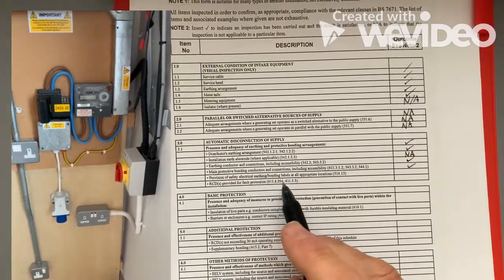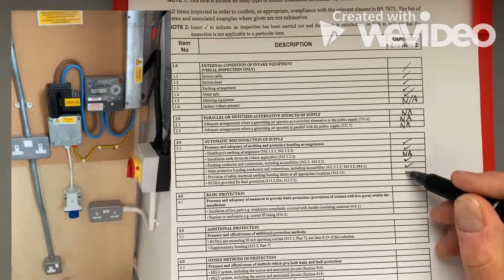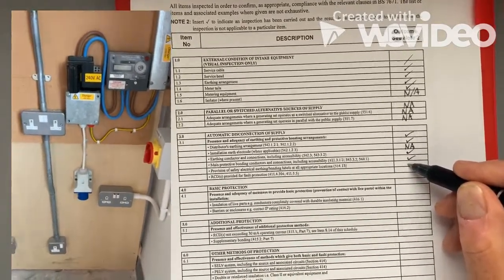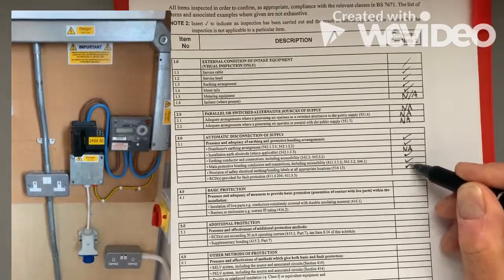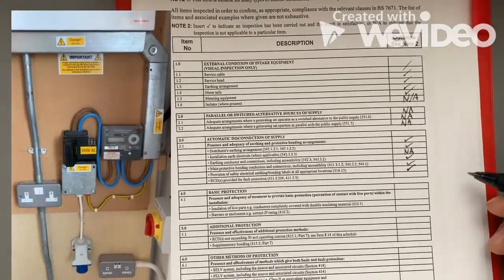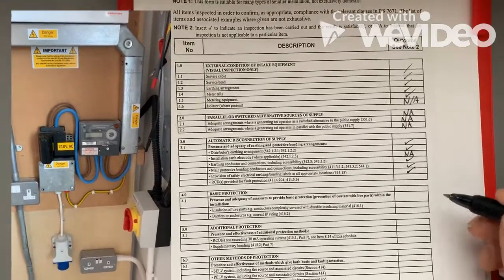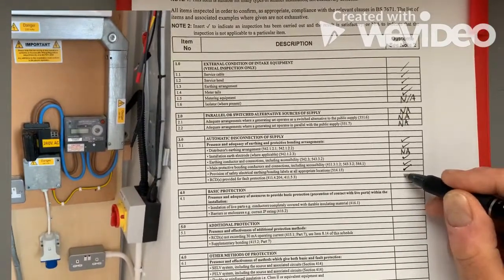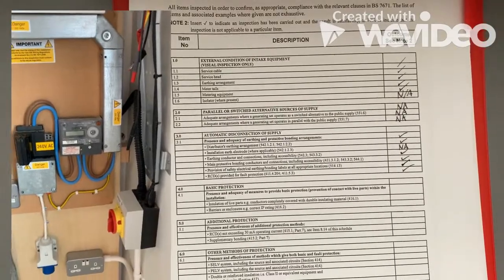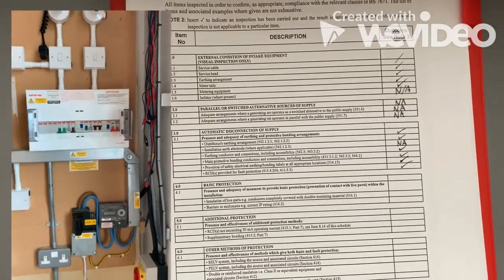Provisions for safety, electrical bonding labels. Now there should be labels on here, and if we have a look we'll find some labels, we can see those. And is there an RCD? And I believe there is an RCD, so we'll just have a quick look at that and we'll see we've got the RCD. So we'll just double check those again.